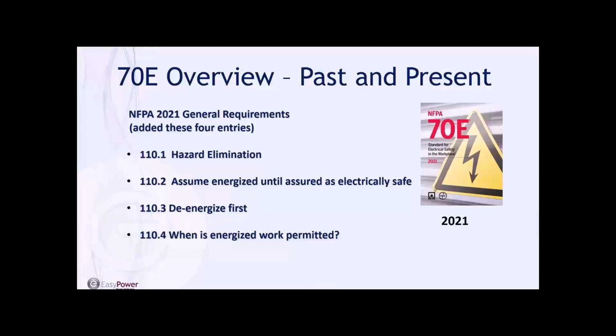Our very first element here is hazard elimination. In order to do hazard elimination, one of the first things that needs to be done is to identify the hazards, and one of the major elements to identify hazards would be the arc flash study itself. So you can see how these various article references will, by their definitions and implementations, reach to other areas and functions within the breadth of the 70E standard.